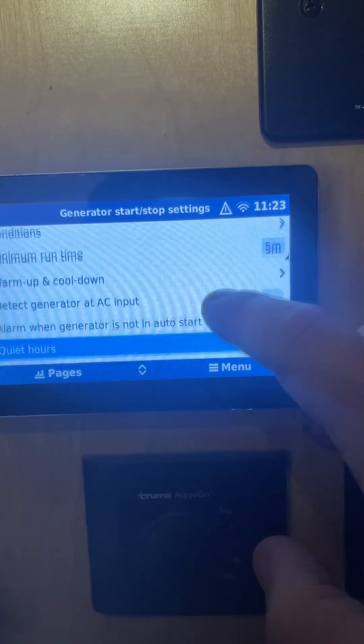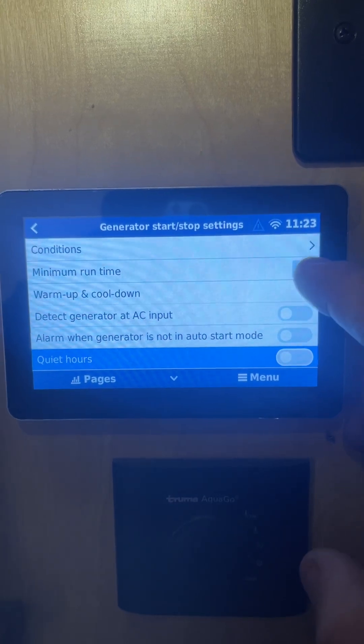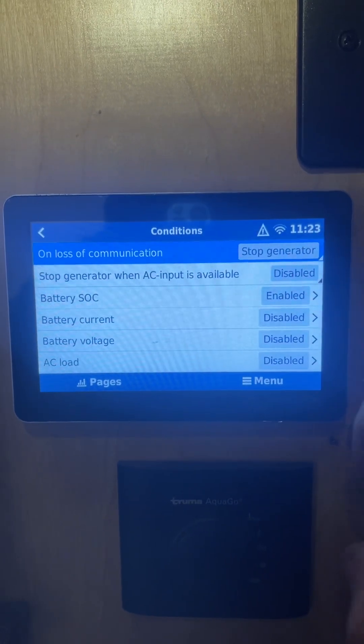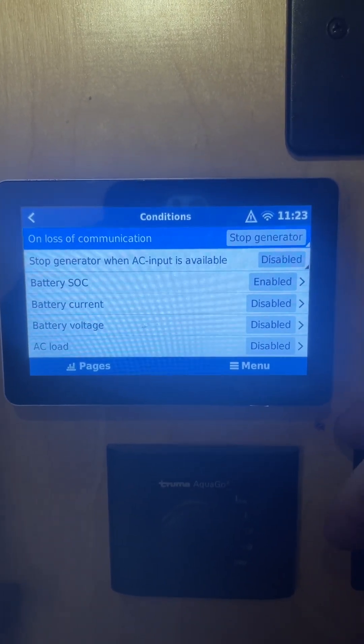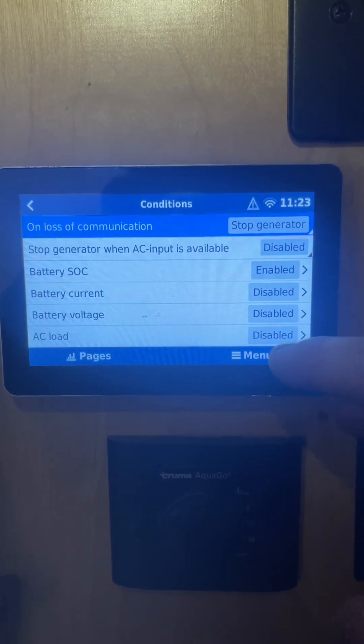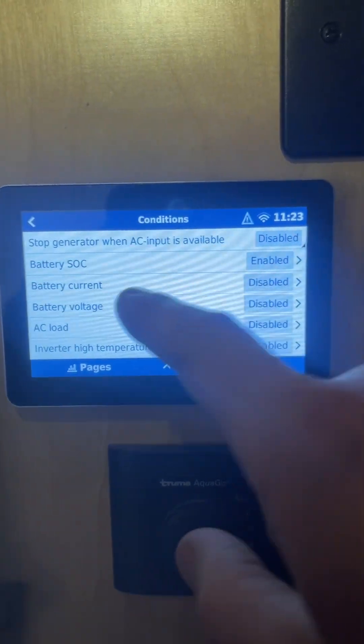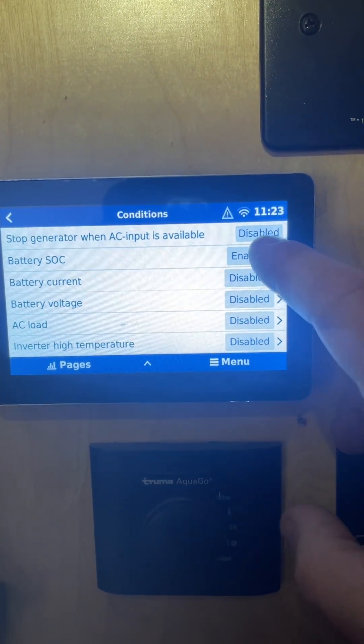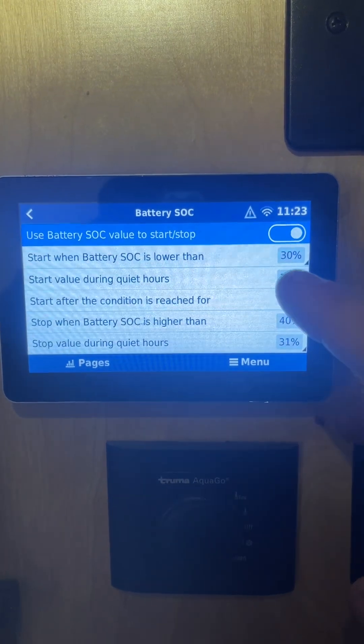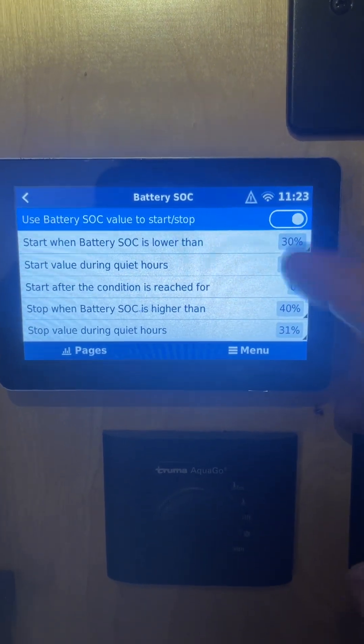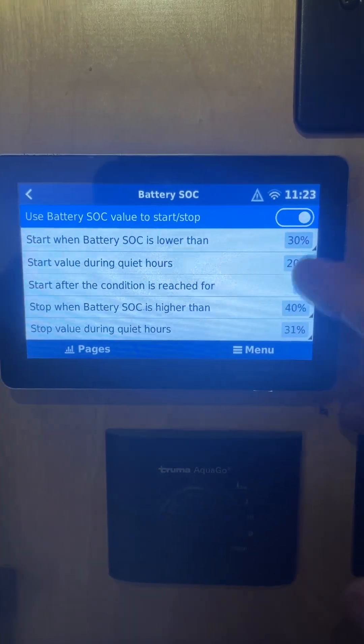The main thing you want to look at is the Conditions section — this is how you get the generator to start and stop depending on what conditions you want. Usually we set it on battery state of charge (SOC), so if you click that, you can tell it to turn on and off depending on the battery's state of charge.